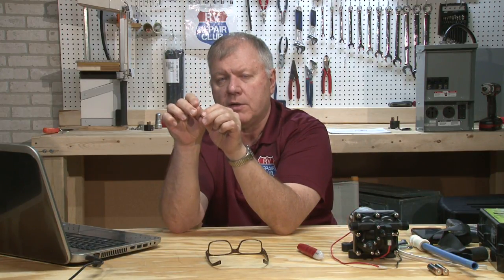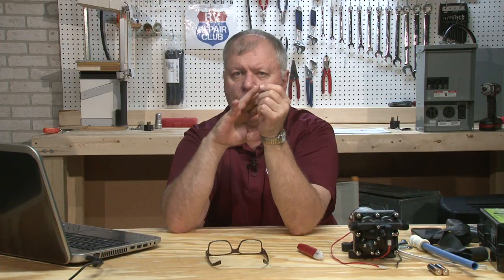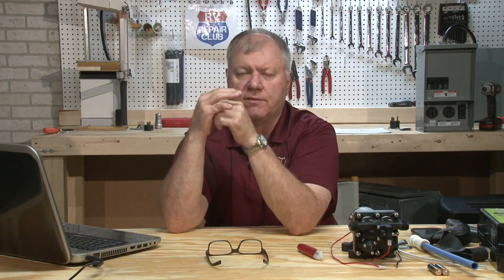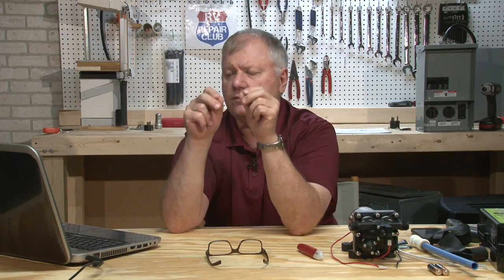So I would go in and take a multimeter and test that on one side of the GFCI you got power coming in, 120 volts. On the other side of it you got power into the GFCIs in there, and just make sure everything's wired up, because the green light doesn't always mean it's working properly or that the GFCI is working. Basically, when something like that's not working, you've got to go in and test voltage.